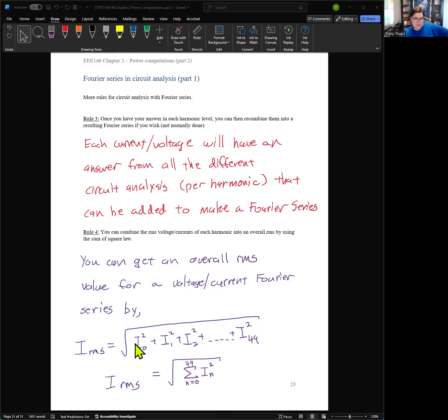A more formal way to write this is I RMS equals the square root of the summation from 0 to 49, where you take each one and you square them and add them together first. So square each individual harmonic current, add them all, and then square root the thing at the end. Okay. This is how you add harmonic currents together. You can't just literally add 1, 2, 3, 4, 5, 6 together arithmetically. That's going to give you really, really wrong answers.